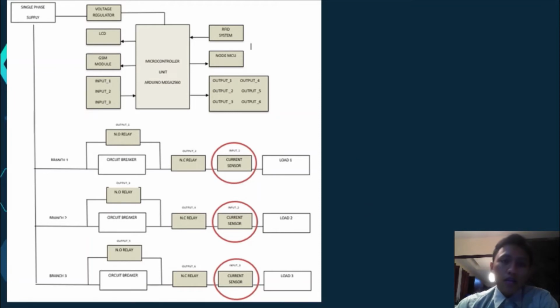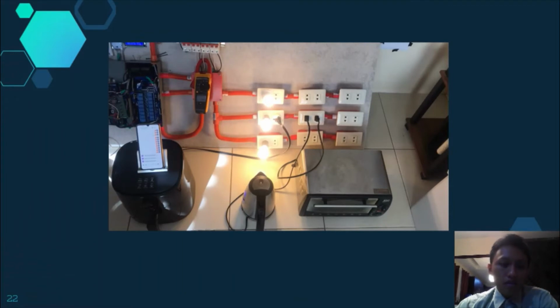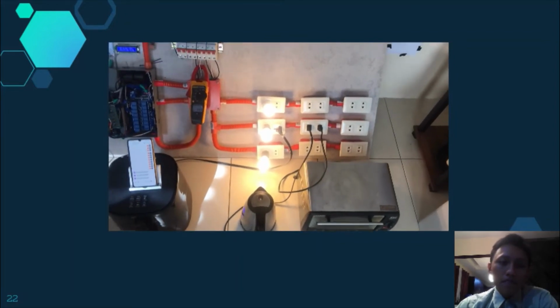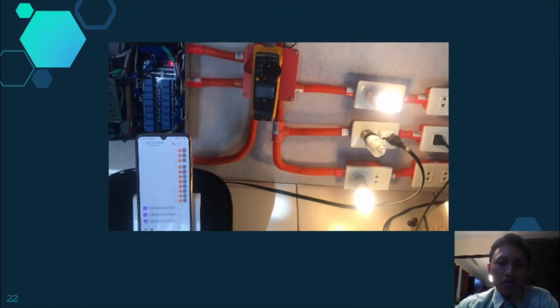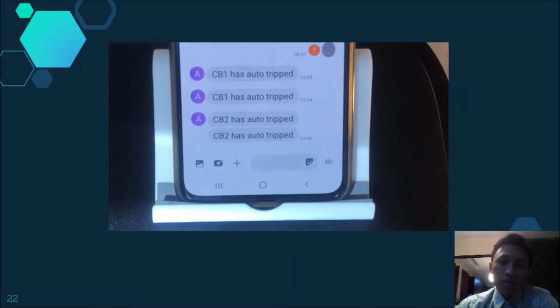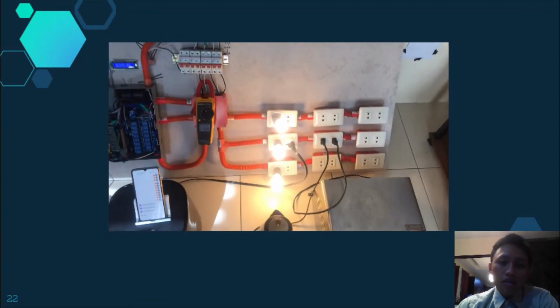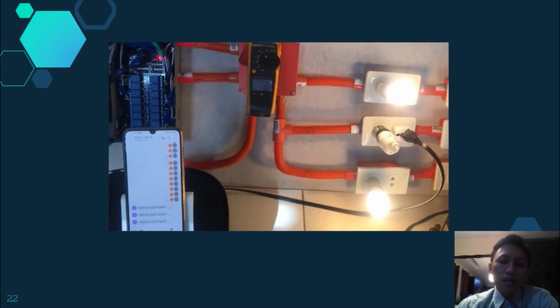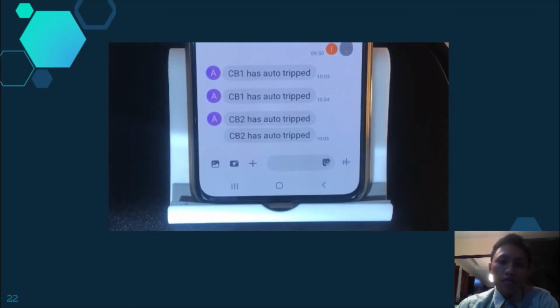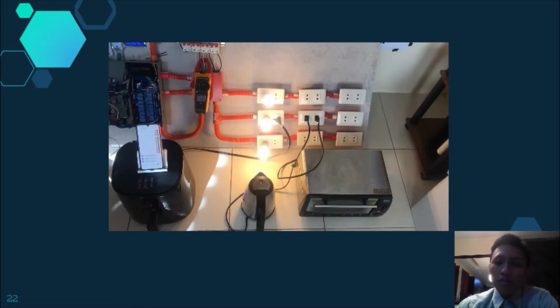To monitor overcurrent, we have placed a current sensor in series with the load. This sensor is capable of measuring the load current. And in this prototype, since we are using a 15 ampere circuit, the maximum load current is set to be 12 amperes. In this video, we'll be demonstrating how this overcurrent is being monitored. So as you can see, here branch 2 is overloaded, so the load current is 14 amperes, and then it automatically tripped, and then after that the GSM module has sent a text message to the registered number.